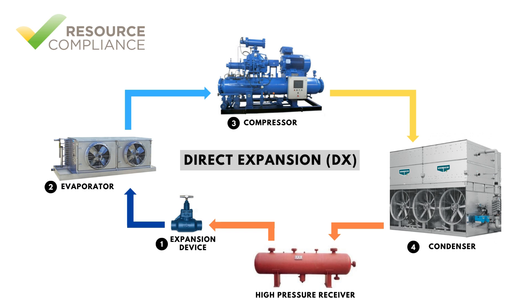Theoretically, a vapor compression system does not require a high-pressure receiver, but due to fluctuations in load and changes in ambient temperature, a receiver provides storage for refrigerant not being used at any given moment. The high-pressure liquid from the receiver is then piped to the expansion device, where we started our process.